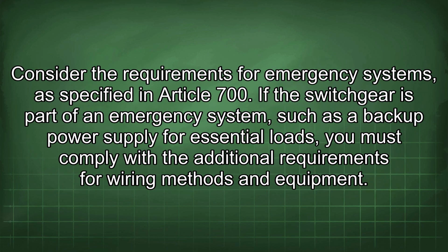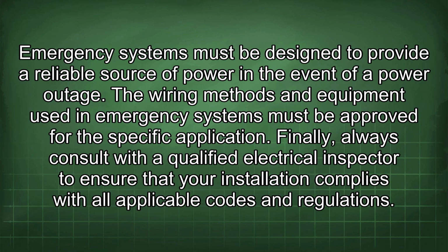Consider the requirements for emergency systems, as specified in Article 700. If the switchgear is part of an emergency system, such as a backup power supply for essential loads, you must comply with the additional requirements for wiring methods and equipment. Emergency systems must be designed to provide a reliable source of power in the event of a power outage. The wiring methods and equipment used in emergency systems must be approved for the specific application.